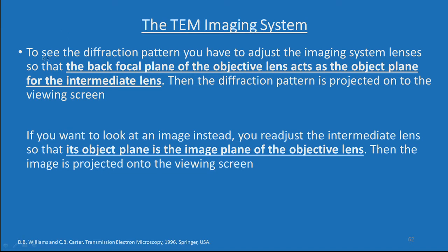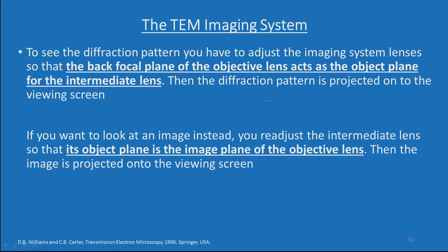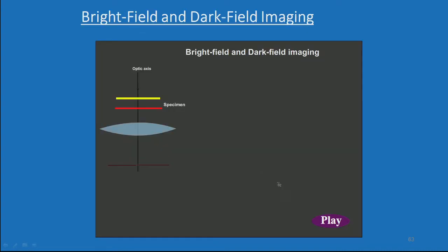To see the diffraction pattern, you adjust the imaging system lenses so that the back focal plane of the objective lens acts as the object plane for the intermediate lens, then the diffraction pattern is projected on the viewing screen. If you want to look at an image instead, you readjust the intermediate lens so that its object plane is the image plane of the objective lens, and then the image is projected on the viewing screen.